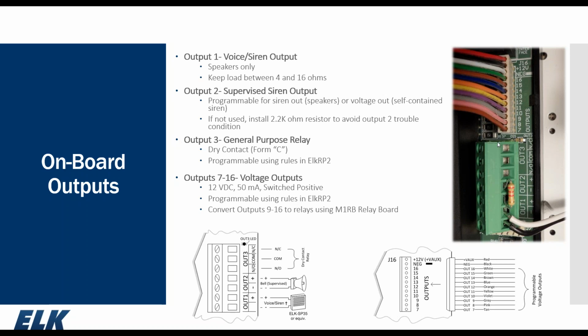Output 3 is a general purpose Form C relay. So it's capable of dry contact, maybe for an overhead garage door to simulate that button press. Or you can control voltage devices up to 24 volt DC at approximately 4 amps. To control output 3, we would use the RP2 software and create a rule to turn that output on and off. The J16 connector right up here at the top of the picture.